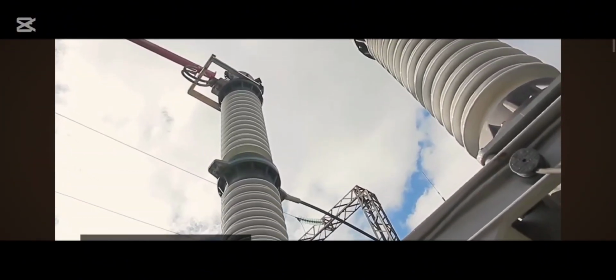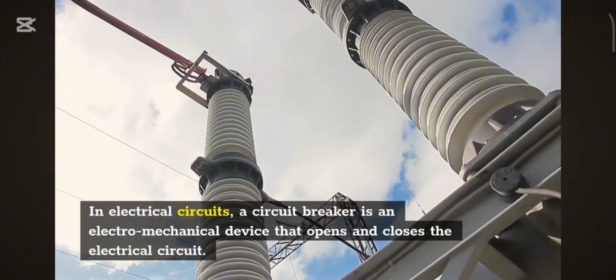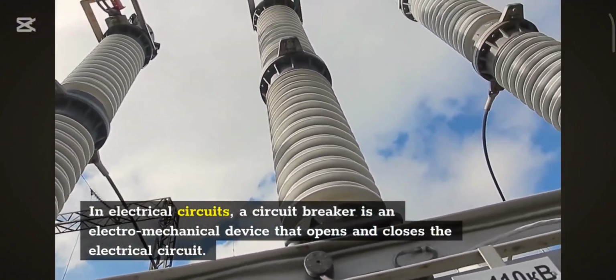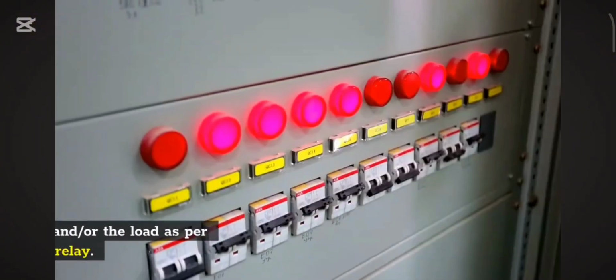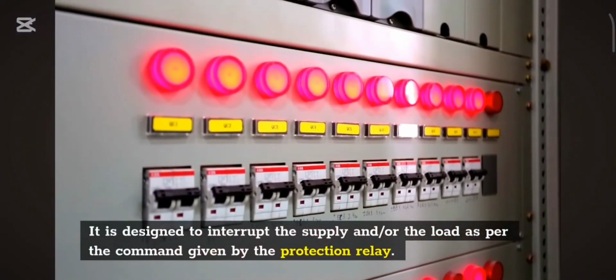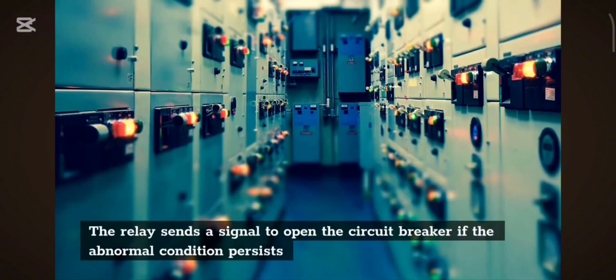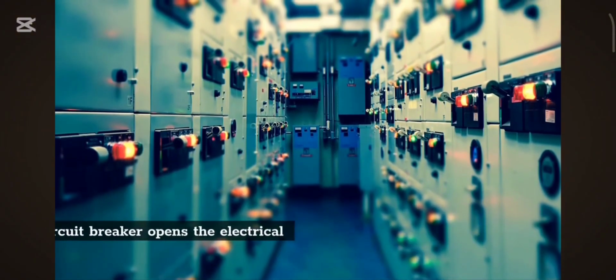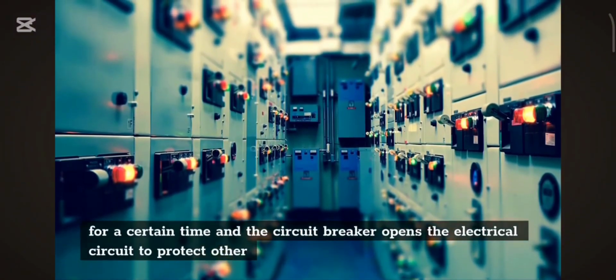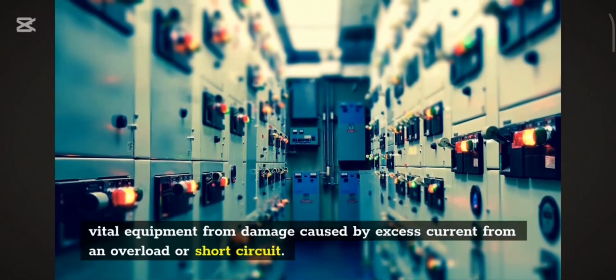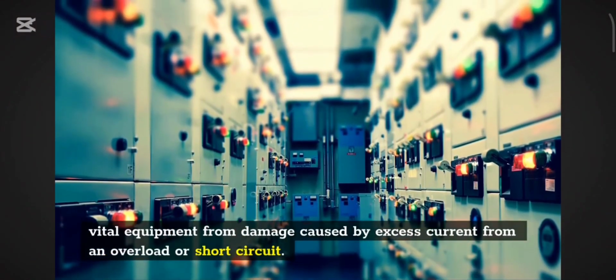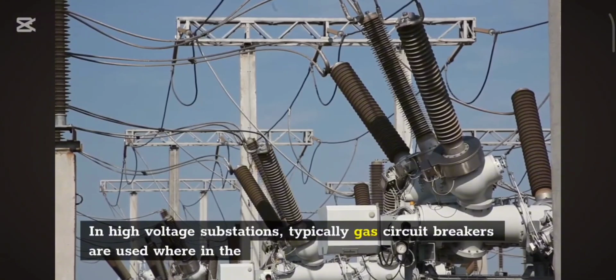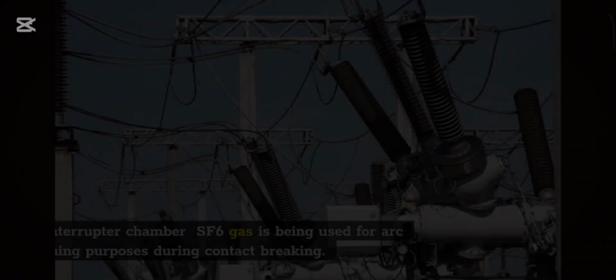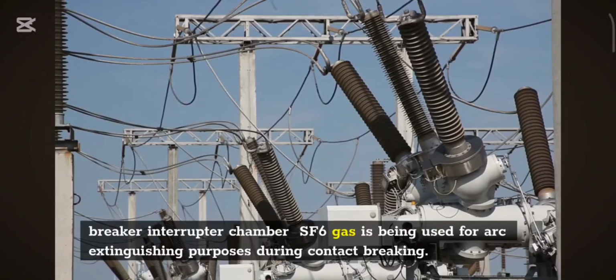Circuit breaker. In electrical circuits, a circuit breaker is an electromechanical device that opens and closes the electrical circuit. It is designed to interrupt the supply and/or the load as per the command given by the protection relay. The relay sends a signal to open the circuit breaker if the abnormal condition persists for a certain time, and the circuit breaker opens the electrical circuit to protect other vital equipment from damage caused by excess current from an overload or short circuit. In high-voltage substations, typically gas circuit breakers are used, wherein SF6 gas in the breaker interrupter chamber is used for arc extinguishing purposes during contact breaking.